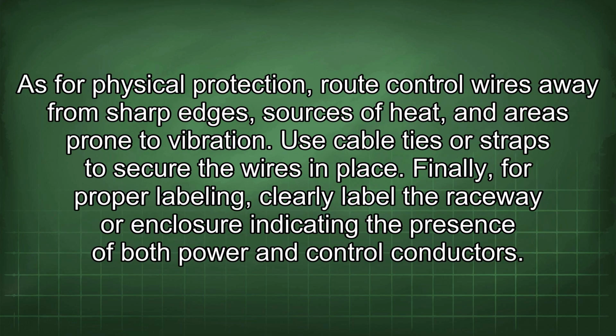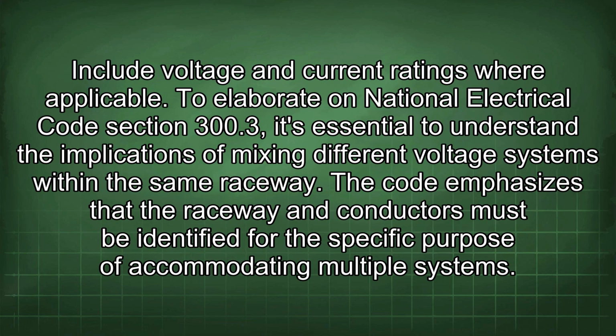As for physical protection, route control wires away from sharp edges, sources of heat, and areas prone to vibration. Use cable ties or straps to secure the wires in place. Finally, for proper labeling, clearly label the raceway or enclosure indicating the presence of both power and control conductors. Include voltage and current ratings where applicable.